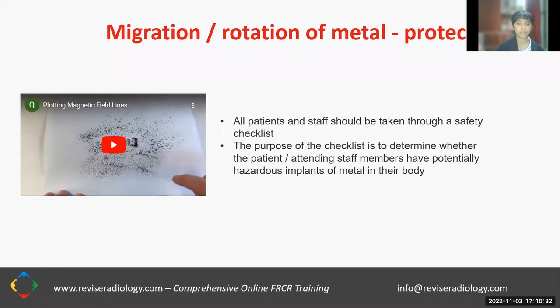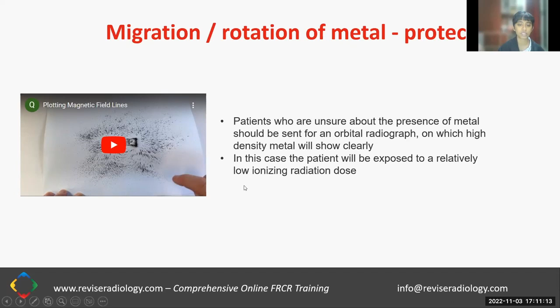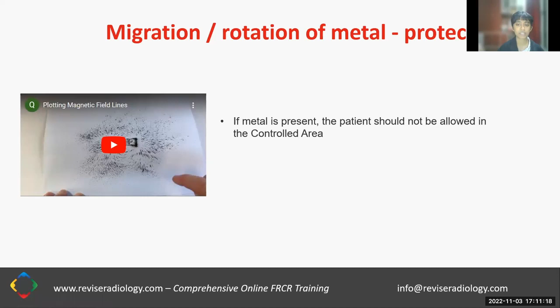Patients who are unsure about the presence of metal, or who are unable to communicate the presence of metal, either because they're unconscious or of unsound mind, and basically if there's no reliable source who is able to confirm whether the patient has metal in their body or not, need to be sent for a radiograph on which high density metal will show clearly. In this case, the patient will be exposed to a relatively low ionizing radiation dose. So the clinicians involved have to take that dose into account when calculating the risk-benefit assessment of carrying out these imaging studies. If metal is present, the patient should not be allowed in the controlled area.